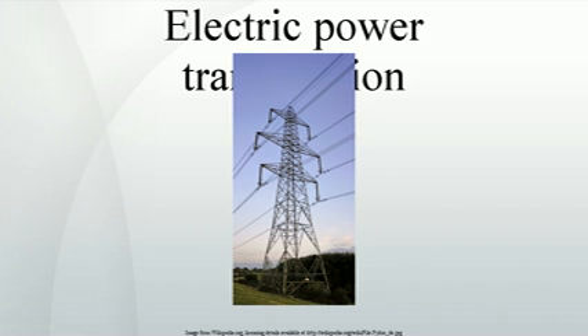It is to reduce the risk of such failure that electric transmission networks are interconnected into regional, national or continent-wide networks, thereby providing multiple redundant alternative routes for power to flow should such equipment failures occur. Much analysis is done by transmission companies to determine the maximum reliable capacity of each line, ordinarily less than its physical or thermal limit, to ensure spare capacity is available should there be any such failure in another part of the network.